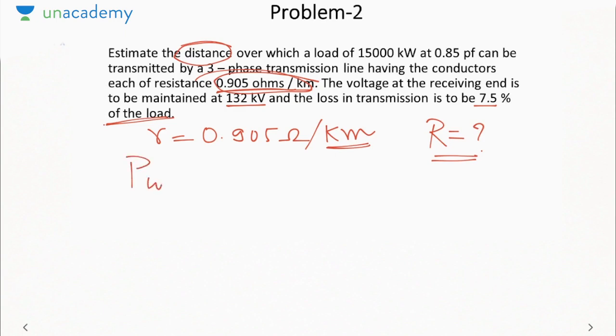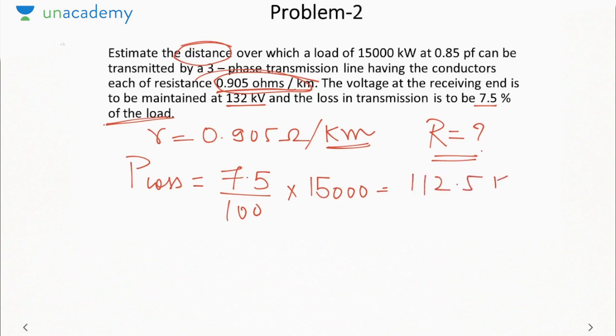So what is the loss? 7.5% of output, which is 15,000. So this will come out to be how much? 112.5 kilowatt. Now to find out the resistance, we must equate it to I square R. For that I need current, and current can be found out from the loading. As I told you, whenever load is given, first find the current.